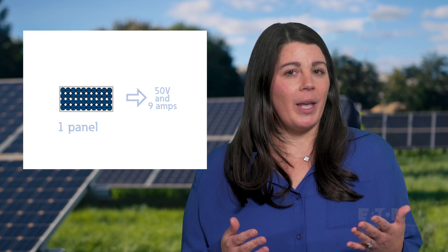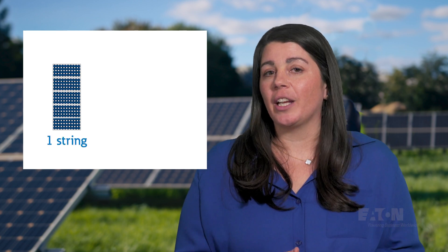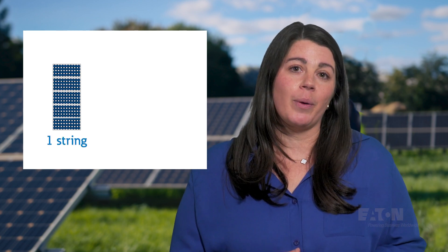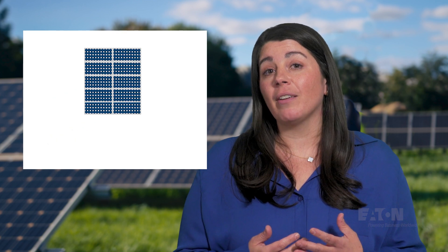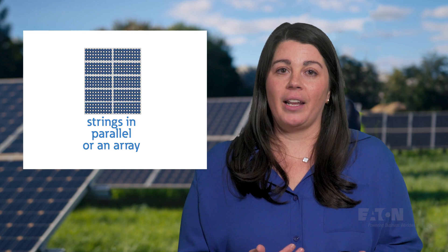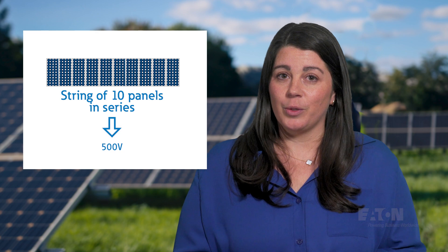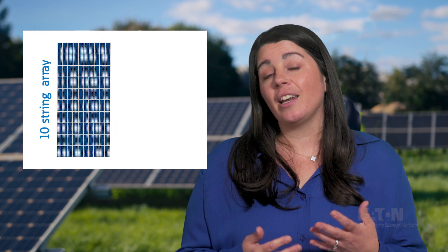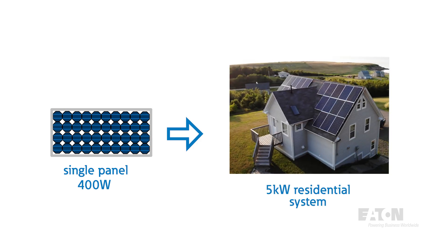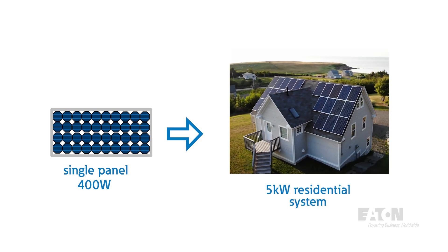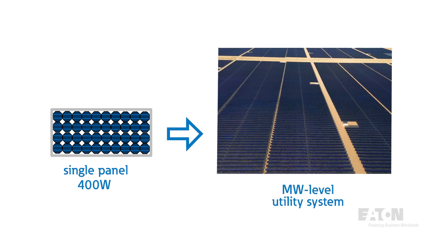So we connect multiple panels in series, which we call a string, to increase the voltage output. We also connect multiple strings in parallel to increase the current output, and we call that an array. So 10 panels in series will create a string that generates 500 volts, and an array of 10 of these strings can generate about 90 amps. This is how we can take a single panel that can generate about 400 watts and scale it to any size system, from a 5kW residential system to a megawatt level utility system.